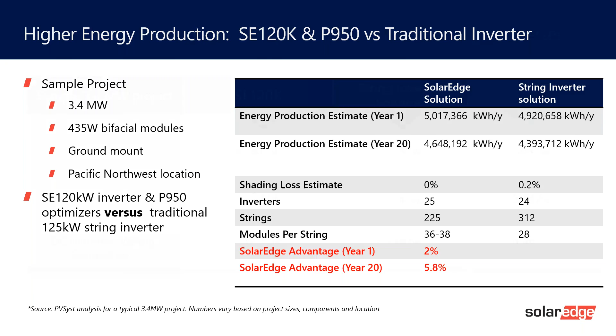If we switch to the next slide on balance of system savings—we reduced the number of strings by about 25 to 30%. That translates into DC cable savings as well as labor savings. For this specific site, we saved almost 2 cents in DC balance of system because of fewer strings, meaning less home run wiring back to the inverter. Of course, if you take out that material, you also save labor as well as material.